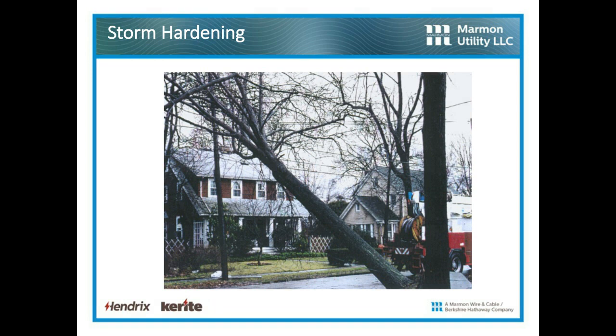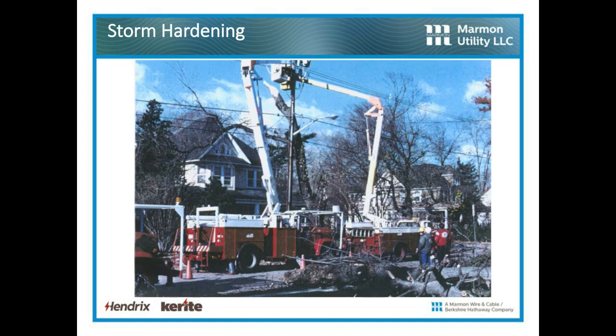But if you check closely, you can see that tree is sitting on the messenger connected to the pole on the right. And out of the picture on the left, it's connected to the pole on the left. The linemen come out. They cut that tree tiny piece by tiny piece so as to not suffer a violent swing of the messenger, creating a safety problem. They've straightened out that pole. They put a new bracket on that pole. And with the equipment handler on the bucket, on that truck, they've lifted that bundle up by the messenger, put it in the parallel groove clamp on the tangent bracket, turn the bolt, and they've never had an outage.